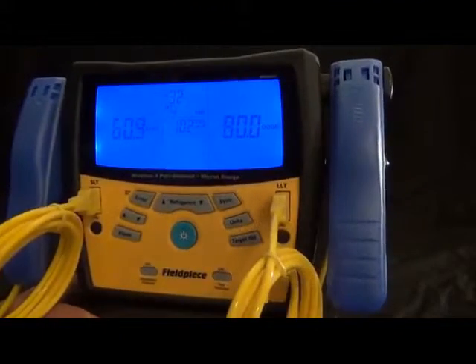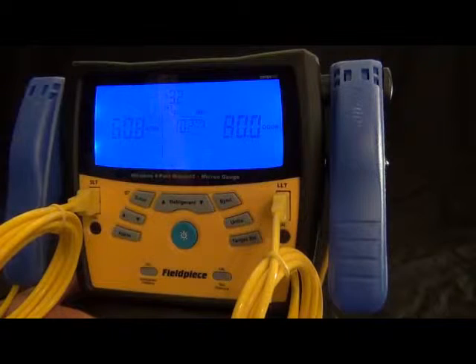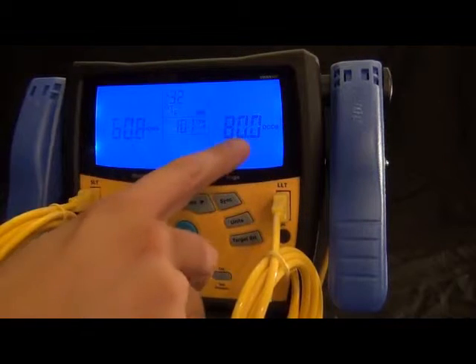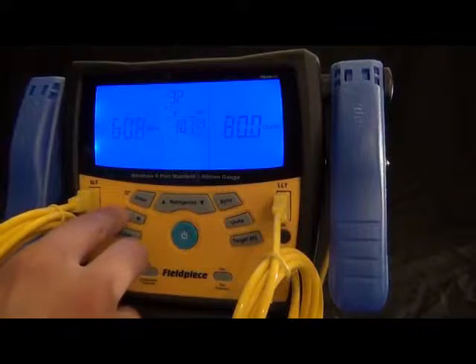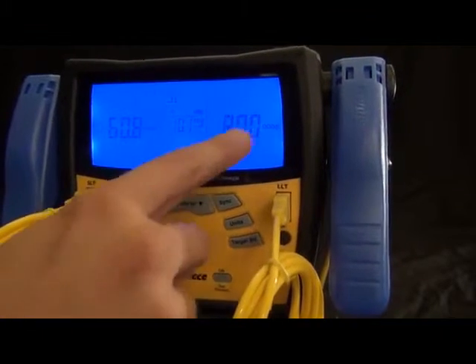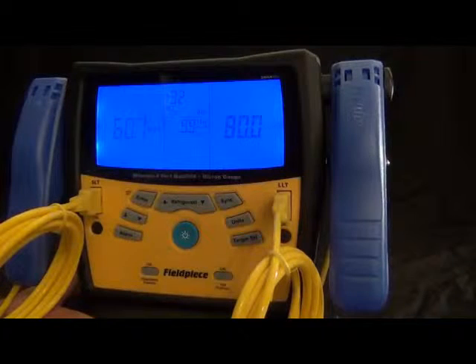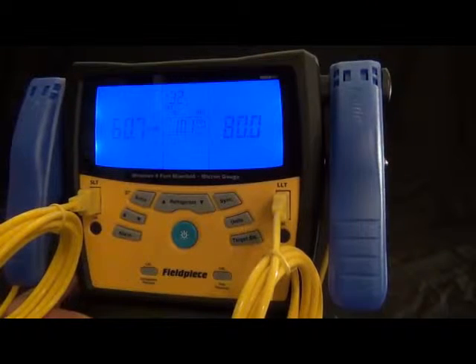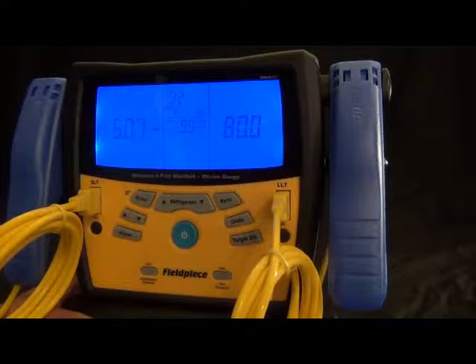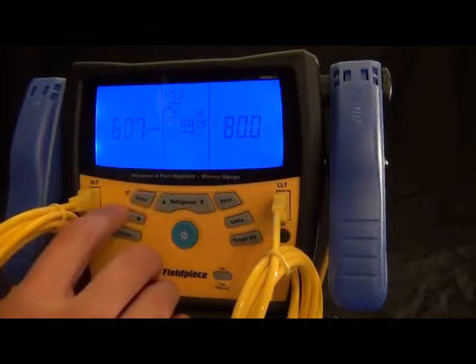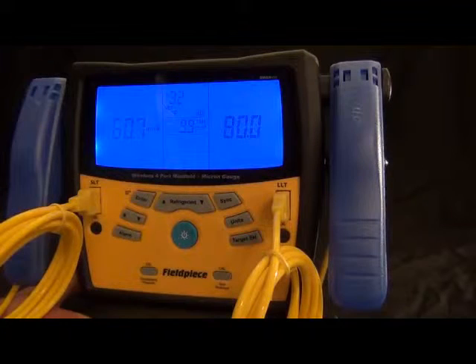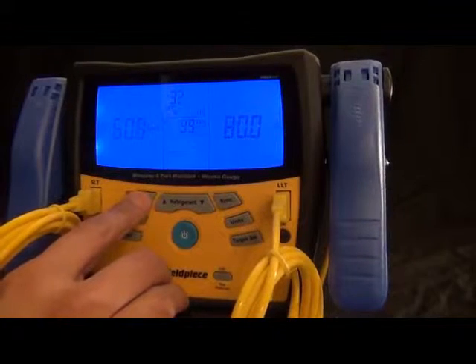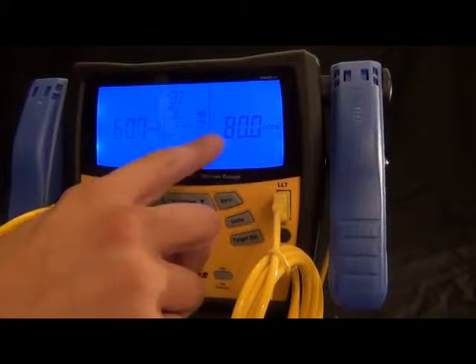Then, I can adjust this as I need. So, let's say it's 85 degrees outside and 84 degrees inside. Then, it'll just automatically calculate my target superheat. Now, you'll notice that it's live, as this number is slightly adjusting, because it is a live wireless measurement. This number will also adjust slightly. So, that's why it's real nice about having the wet bulb wireless like that. As you can see it live, if something does change in the system, you're going to know, and it's going to adjust properly.